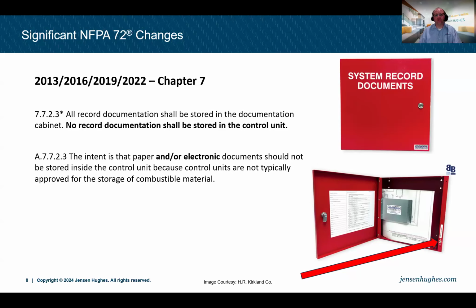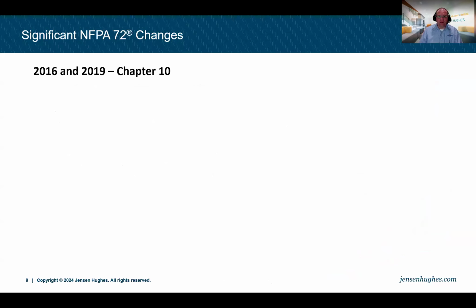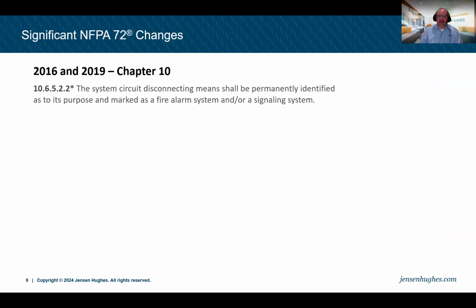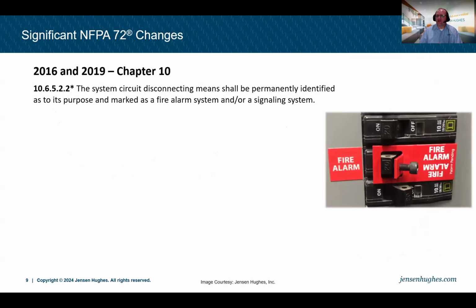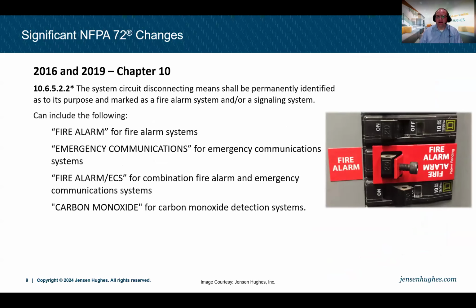But we never want to store that paper documentation within the fire alarm control unit. In 2016, we had an item that was added in Chapter 10 that talked about the circuit disconnecting means of a fire alarm system. And it requires it to be permanently identified as to its purpose and marked as a fire alarm system. So you see a picture of a good example of this kind of documentation inside.